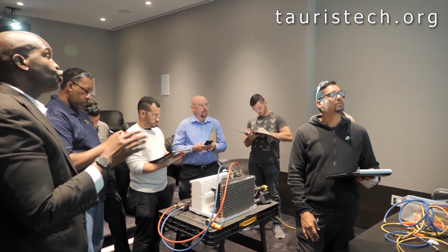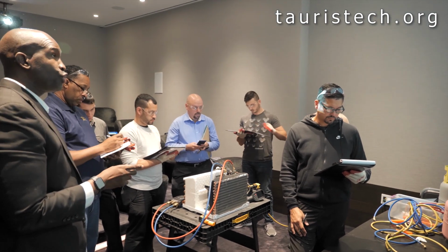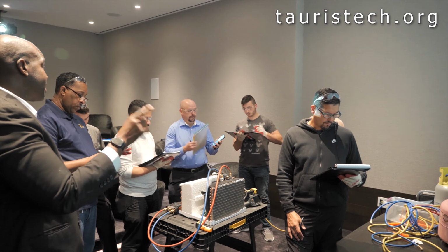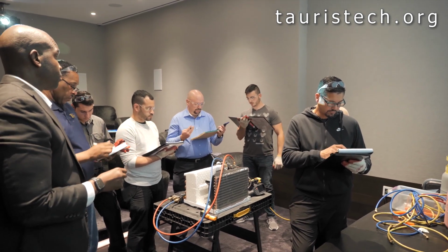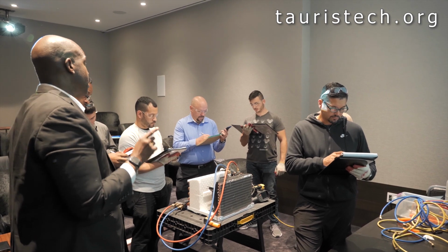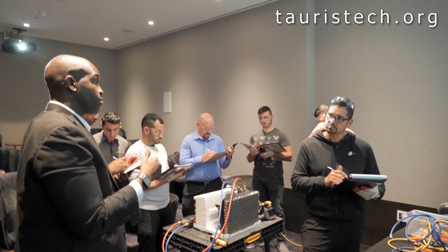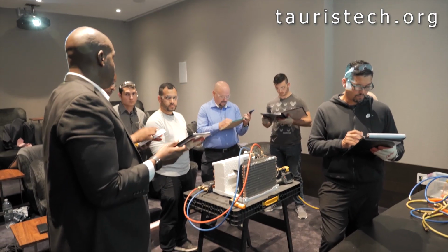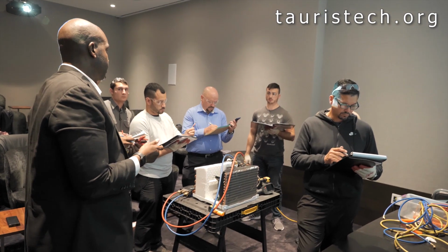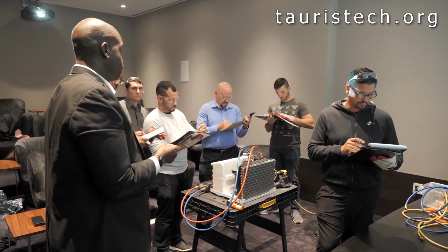Now, 2 subtract 1. What was the reading that you guys had for number 2? 66. What was the reading you had for number 1? 44. So what is 2 subtract 1? 22. There's a word we give that. You guys know what the word is? Superheat. That is our low side superheat.